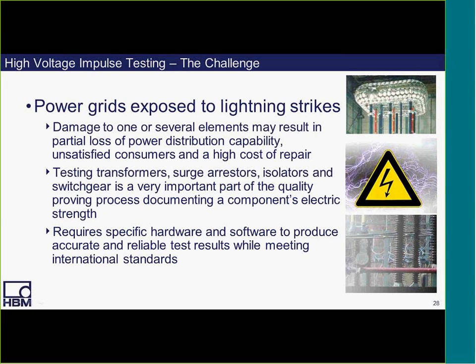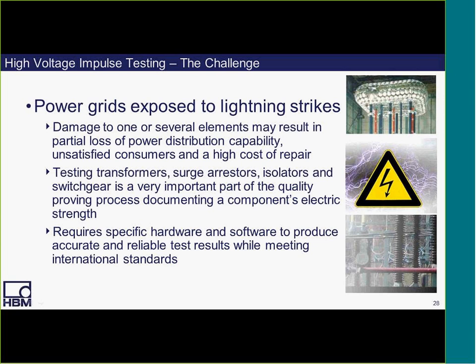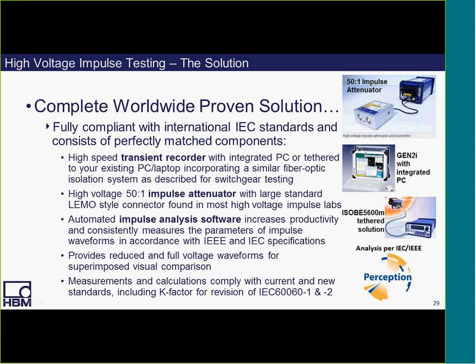So this requires, again, specific hardware and software to produce accurate and reliable test results while meeting the international standards. Again, here in the high voltage impulse testing application, there is a complete worldwide proven solution that is fully compliant with international IEC standards and consists of perfectly matched components, which is a very important part of this test. A high-speed transient recorder with integrated PC, or tethered to your existing PC or laptop, is available, incorporating a similar fiber optic isolation system as described for switchgear testing.